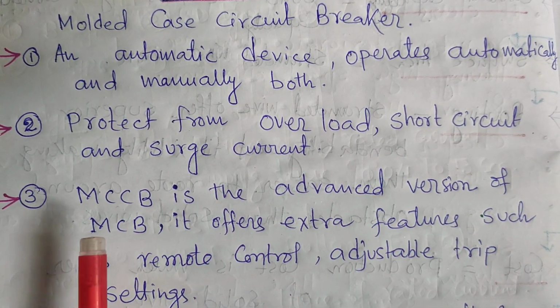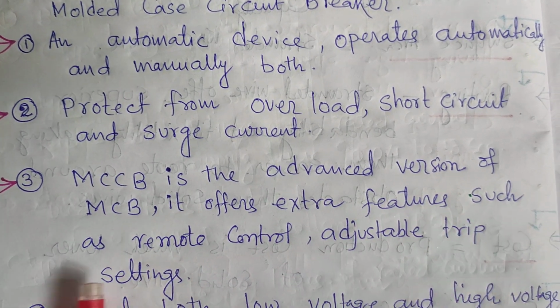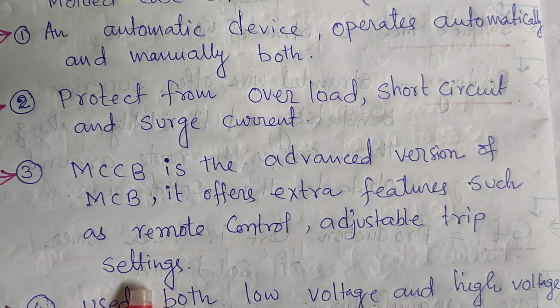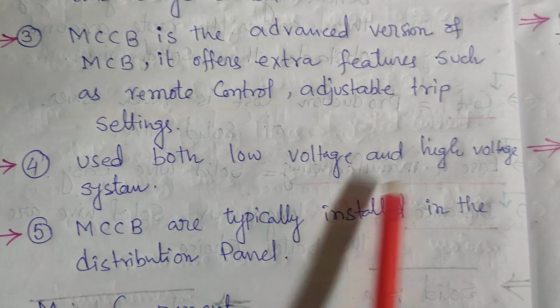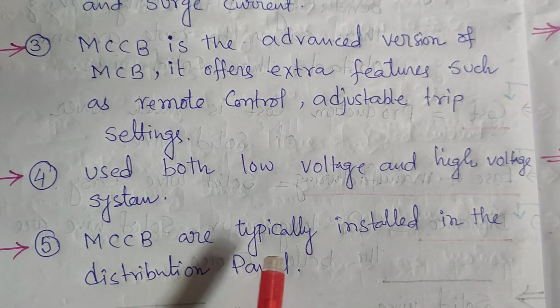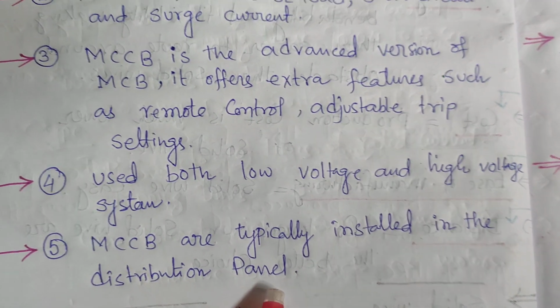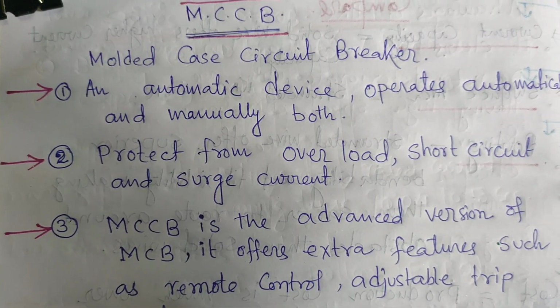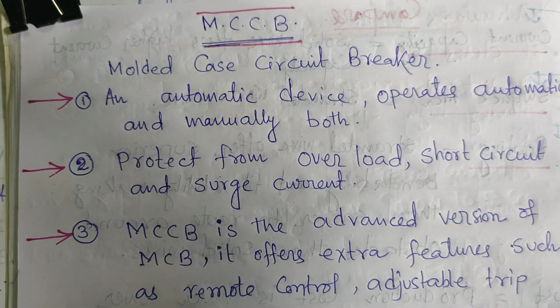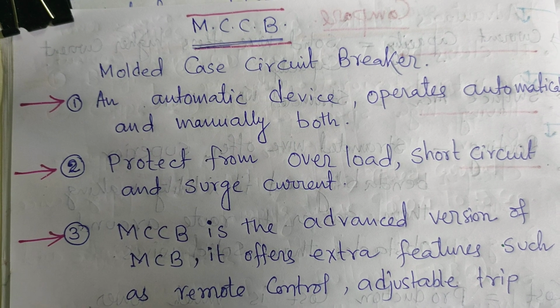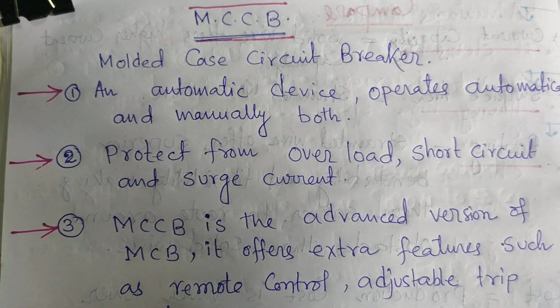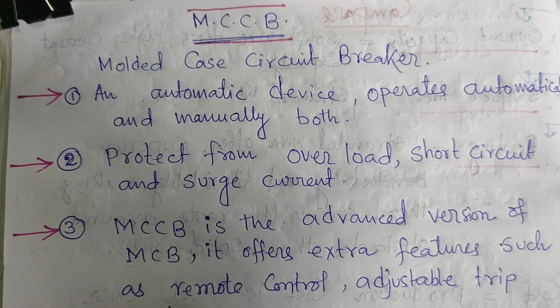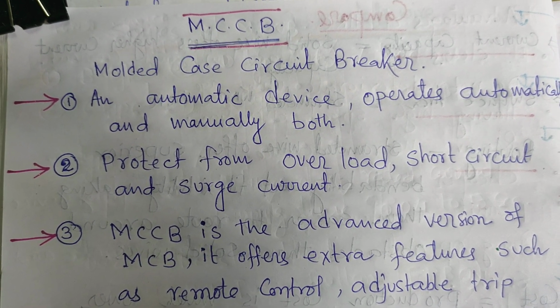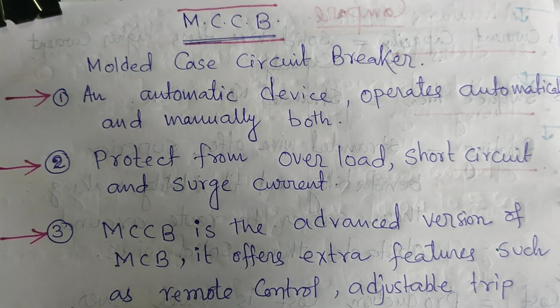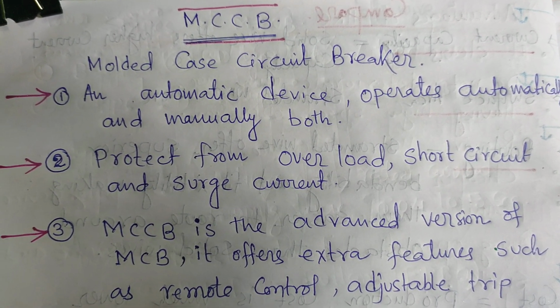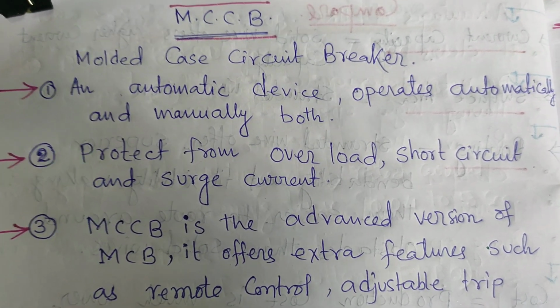MCCB is the advanced version of MCB. It offers extra features such as remote control, adjustable trip setting, etc. It is used in both low voltage and high voltage systems. MCCBs are typically installed in the distribution panel. Inside the substations, it is used in the ACDB, that is the AC, alternating current distribution board. We have already discussed short circuit and overload protection. It is an electromechanical device and its short circuit and overcurrent protection range is from 63 ampere to 3000 ampere. By installing this type of protection inside a circuit breaker, it obviously enhances operator safety.